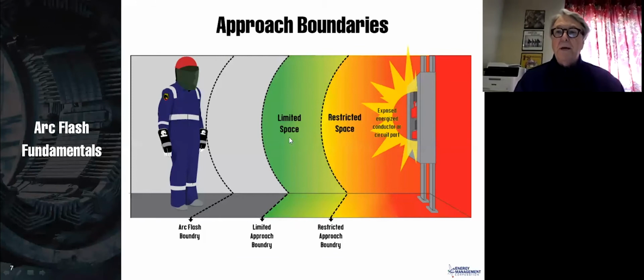The limited space and the restricted space, which for most low voltage systems, the limited is 3.5 feet and the restricted space is 1 foot. They are based upon shock. And if you cross the limited space, you must be qualified or with a qualified person. If you cross the restricted space, you must be qualified and have the appropriate PPE.